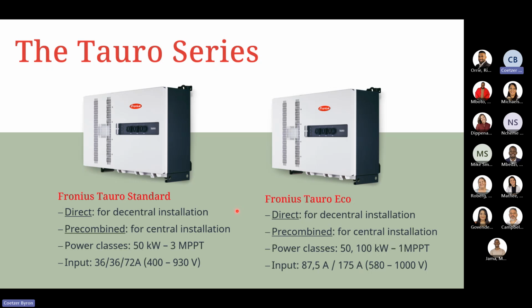For the Tauro series, we have two different variations. So we have what we call the Fronius Tauro Standard. So this can be available for direct or pre-combined installations, depending on your needs for the client. And this is only available in power class of 50 kilowatts, but you've got 3 MPPT inputs on the unit. So the MPPTs are split. So you got 36 amps split between PV1 and PV2, and then PV3 would have then the combined 72 amps, for example. And this is an input voltage range of 400 to 930 volts. So depending on the power class that you're using, but again, we always recommend to make sure that you are above this 400 volt input side, also for the usable range for the unit itself.